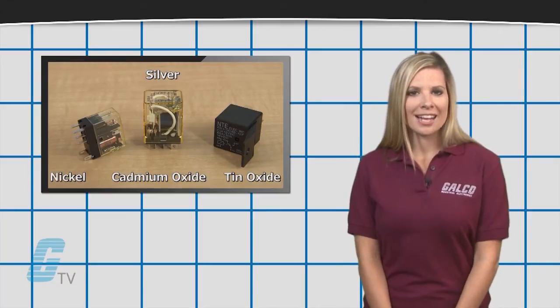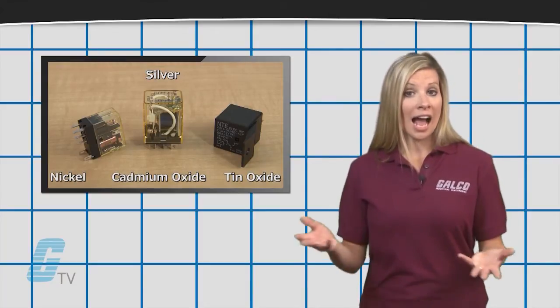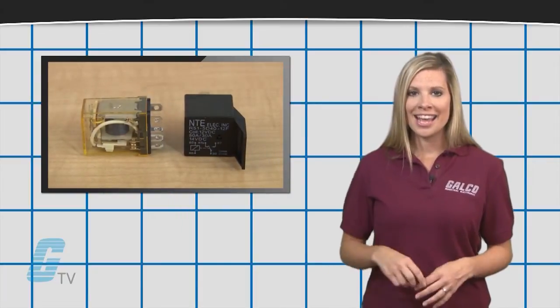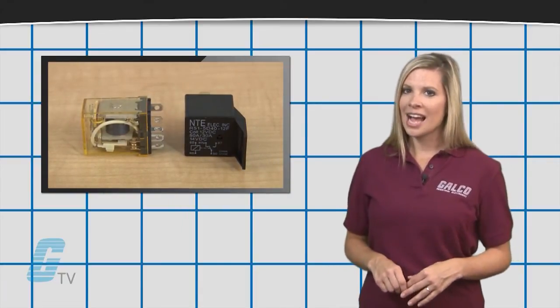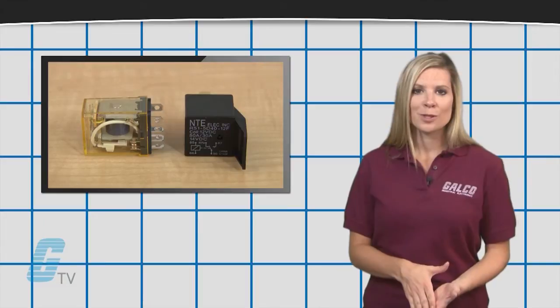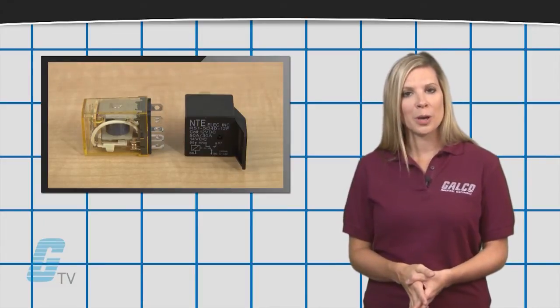The silver base contacts are resistant to welding at high loads, with the silver cadmium oxide and silver tin oxide contacts being ideal for switching inductive and motor loads.